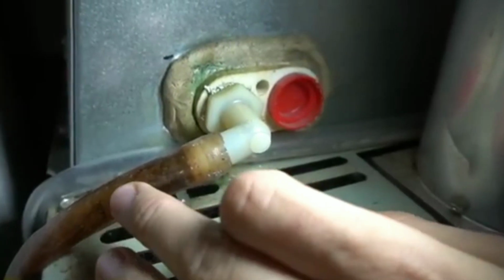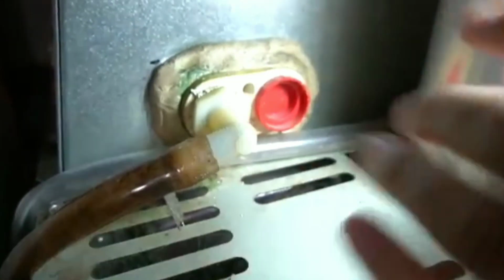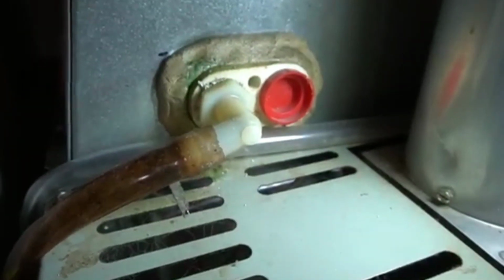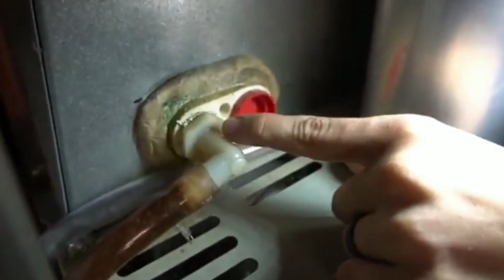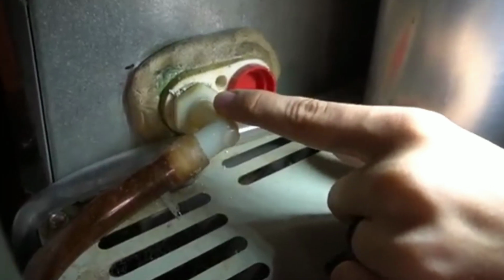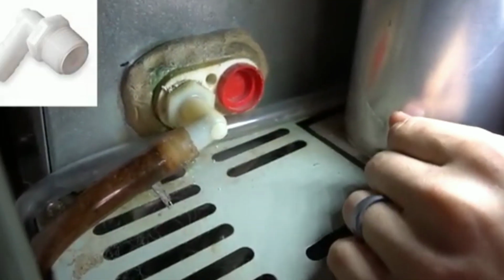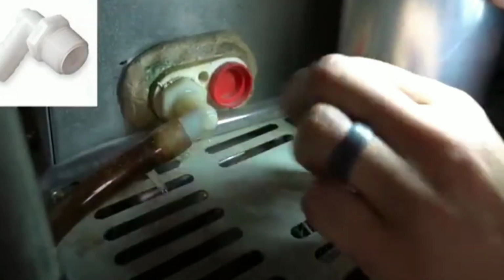And if the water has nowhere to go, it'll start to overflow and go all over your furnace, and you're going to see a puddle underneath your furnace, and that can damage the control board and other furnace components inside. So clean out the hose, make sure the hose is clear. Another thing you could do is take off the hose and then unscrew this fitting. And sometimes the fitting itself inside of here gets plugged up. So as preventative maintenance, you can clear the hose and then take this fitting off, or if you don't want to take it out, you can just either blow backwards through it or stick a wire into it.